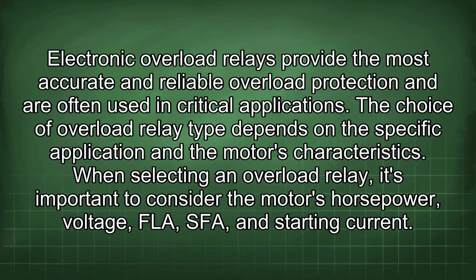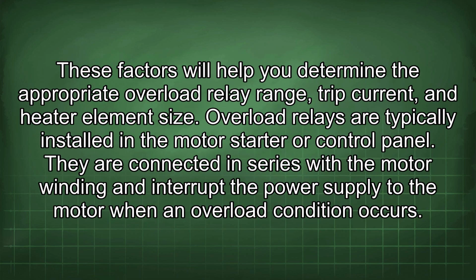When selecting an overload relay, it's important to consider the motor's horsepower, voltage, FLA, and starting current. These factors will help you determine the appropriate overload relay range, trip current, and heater element size.